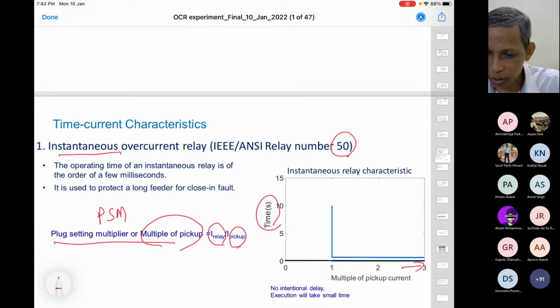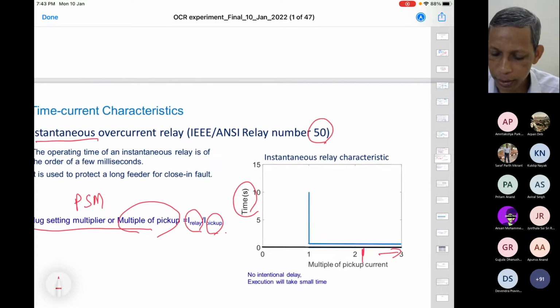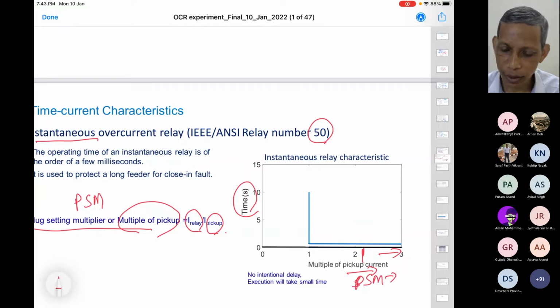So relay current, whatever current is going to the relay, meaning the system side current or fault current, is divided by the pickup. Suppose I have a pickup of 8 ampere, then I will divide by 8. Suppose I have a pickup current of 4 ampere, I will divide by 4. So it shows how many times the pickup current the relay current is at this fault. This is called the multiple of pickup current, or PSM, not the relay current. It is normalized to allow comparison between different characteristics. And then this is time.